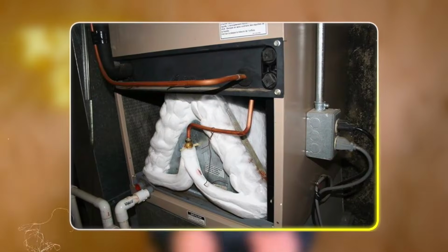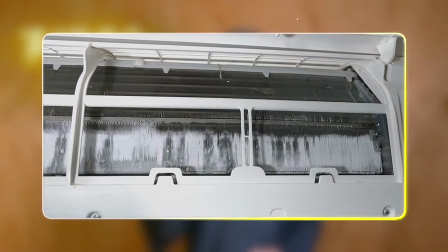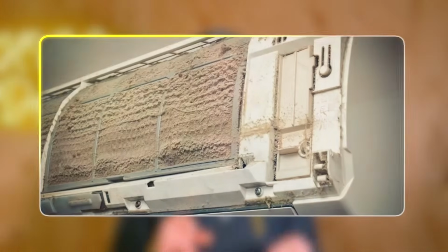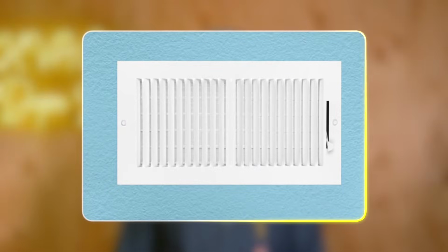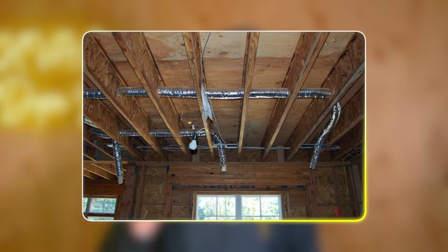So let's talk about the first culprit that almost always is the reason your system is icing, and that is airflow. Contrary to what you might think, when your system is icing, it's not as complicated as you might think, where you might think there's actually something wrong with the system. A lot of times it can be something as simple as a dirty filter or too many registers being closed, or even undersized ductwork, which we'll talk about a little bit later in the video and how you address that.